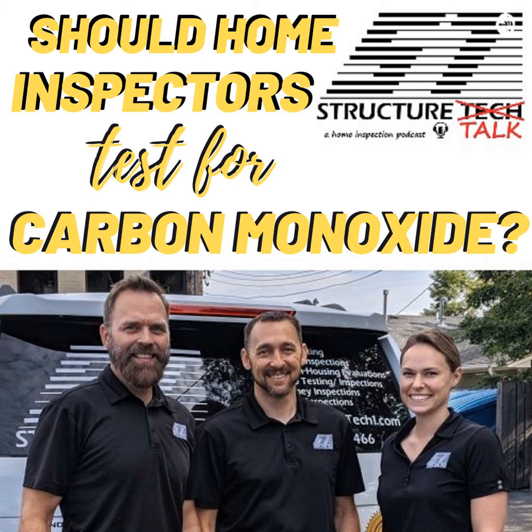Yes. And so if you do test, and if you use diagnostic equipment for testing, or a gas analyzer, I should be more specific so people don't get upset. If you use a gas analyzer and you get to 400 parts per million when the furnace is running at high fire, that's a problem. Everybody agrees to that. Yes, that is a published standard that is in writing. It's in the Minnesota Fuel Gas Code.